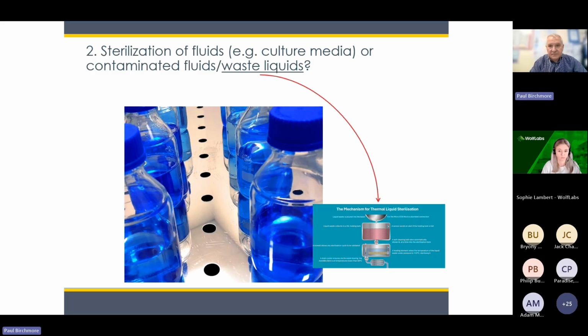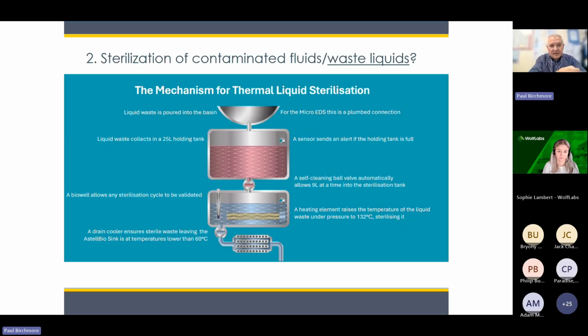Just as a final thing, I'm running over slightly, this thing I mentioned right back at the beginning about liquids. So we've done the clean liquids, the bottled media in the Duran bottles. But if it's dirty media, there is a potential alternative way of doing it, because at the moment you load your dirty bottles of liquid into the autoclave just as you would your clean bottles. But there is an idea that we've come up with whereby you literally pour the liquid into a receptacle at the top there, that's representing a sink, and it falls down from the top of the unit, from the sink area into the initial holding tank, and it waits there until it starts a process.